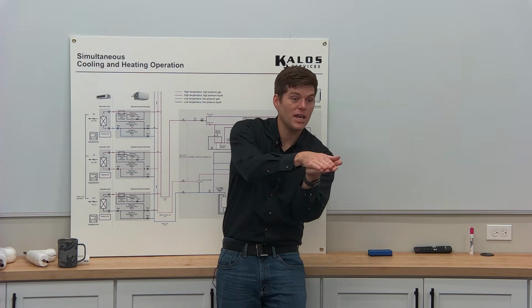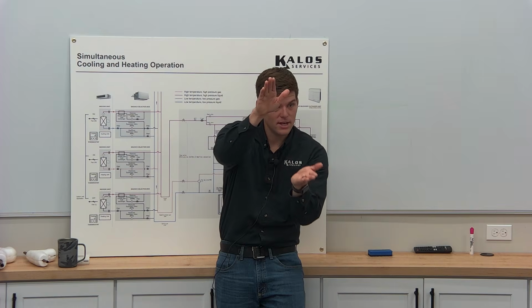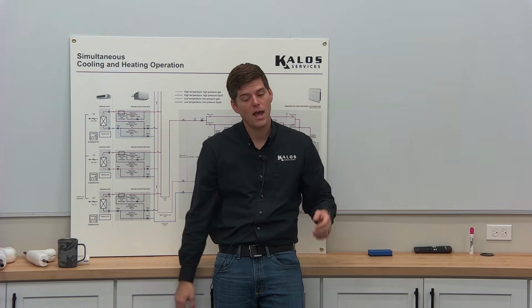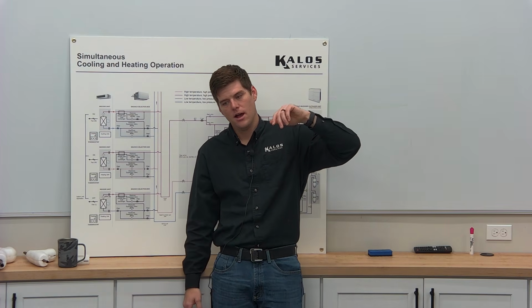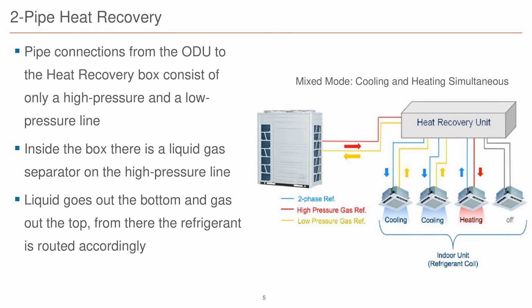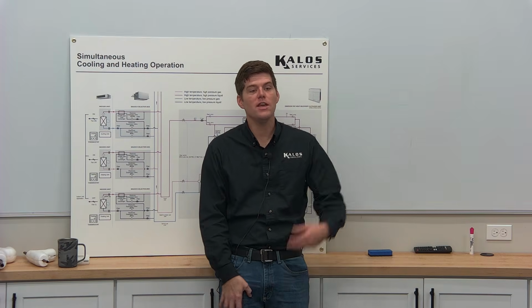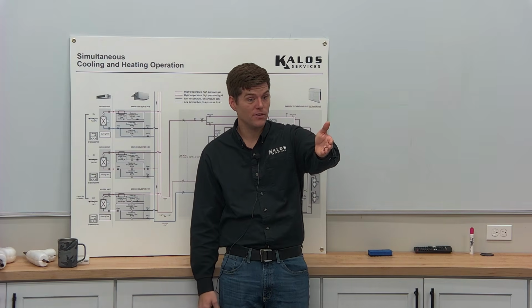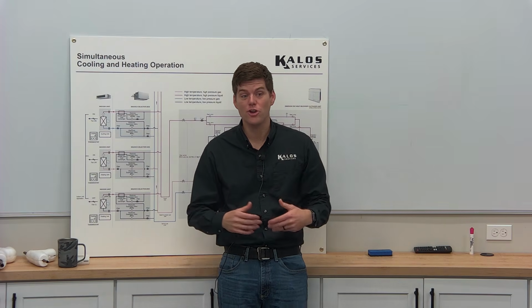Right. It skims that hot gas off the top, takes the liquid from the bottom, and then it'll actually take some of that hot gas. Let's say one indoor unit's calling for heating, as you see here, and two are calling for cooling. It'll take that hot gas, run it through some actual heat exchangers that are built into the box, and create its own liquid, and then feed that liquid to the indoor units. So even the hot gas that's being delivered to the box can still all be turned to 100% liquid in the process.